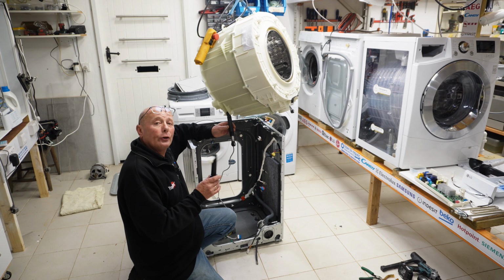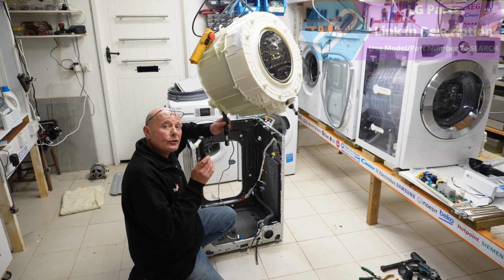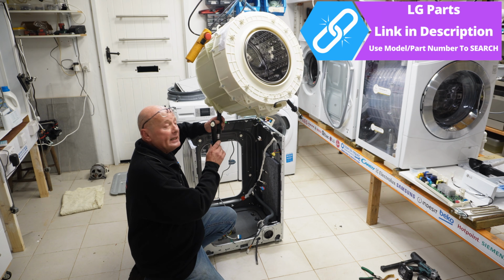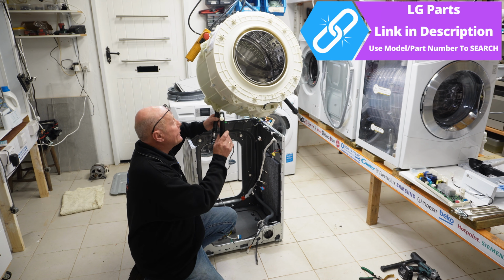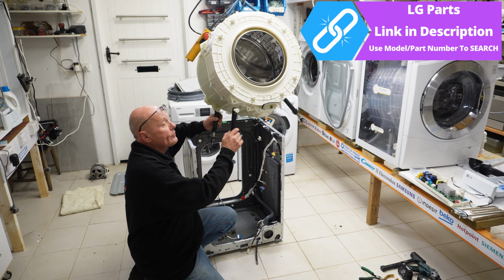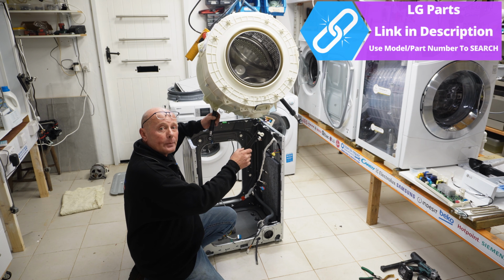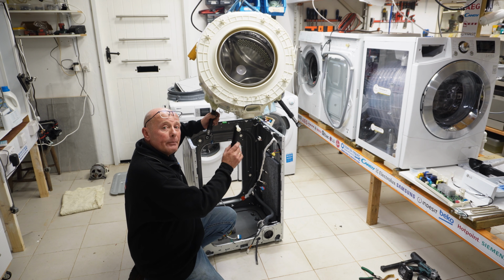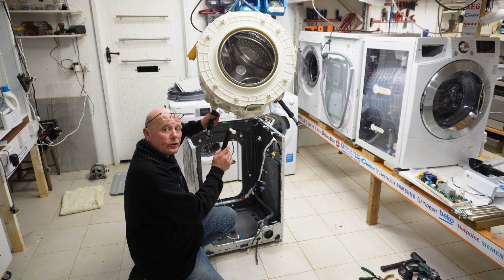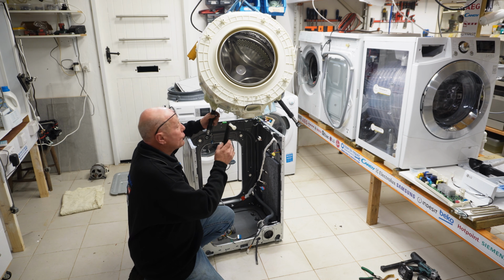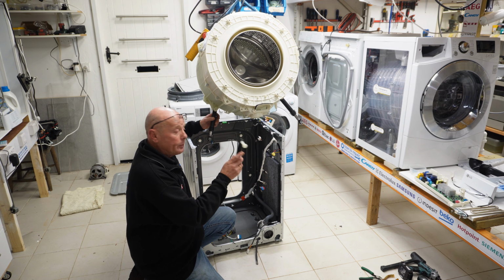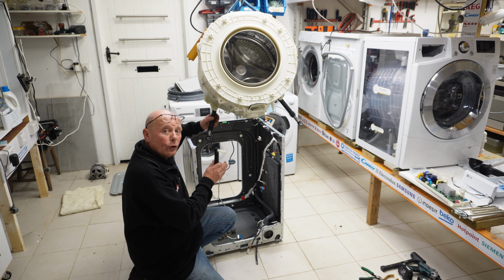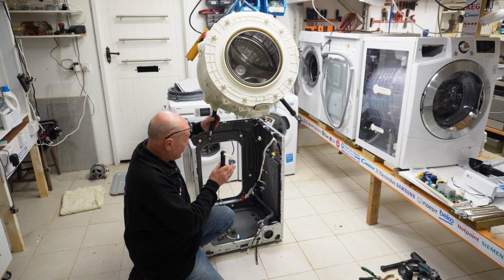Okay, on some models of LG machines, the suspension legs could be different part numbers, because we have two suspension legs on one side of the machine and one suspension leg on the other. And it may be a different type of pressure system that's related to that shock absorber. So do check the part numbers. But on this machine, all the suspension legs were exactly the same.